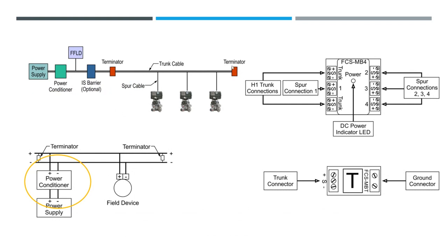Here we have the end of line resistors, or the terminating resistors. I tend to call them end of line resistors, but terminating resistors. The value of these terminators is the same value as the impedance rating on the cable spec. So a 100 ohm impedance cable is going to require a 100 ohm terminator resistor.